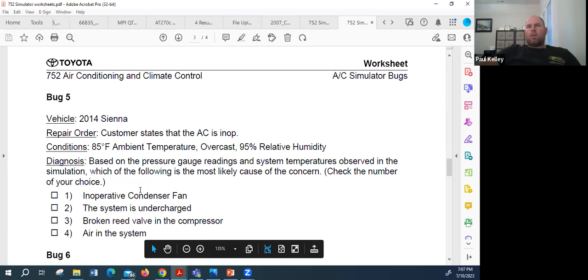So like in this one, for example, our options were, well, we kind of know it's that issue, not enough refrigerant flowing through. It could be undercharged, or it could be a restriction. The reason it's not undercharged is because we check the static pressure. The reason I'd go with a restriction is because we check the temperature right there on the TXV. This one's cool because it lets you do tests. On the ASE, they wouldn't be able to do that.